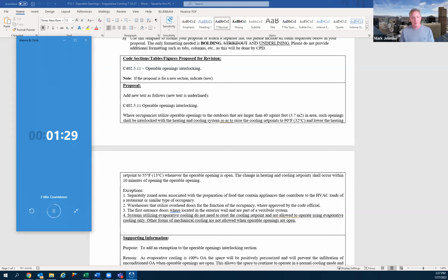We've applied this many times in lots of buildings, and it really reduces cooling compressor hours in just any standard building. But when you're operating that evaporative cooler with mechanical cooling, you need relief.